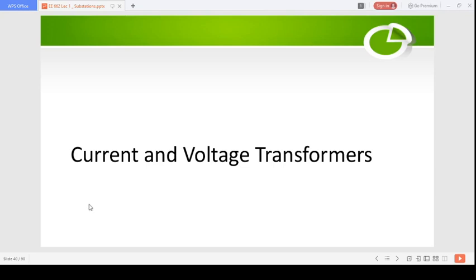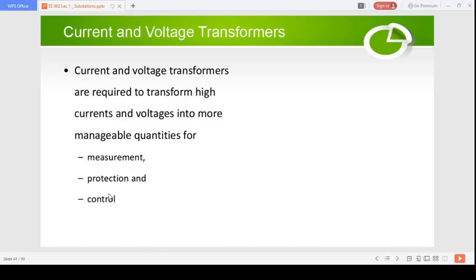Okay, so the next type of devices that you can find in the substation are current and voltage transformers. They are used for measurement purposes. They convert the higher voltages and currents typically available in the bus bars in the substation into more manageable quantities to facilitate measurement, protection and control.